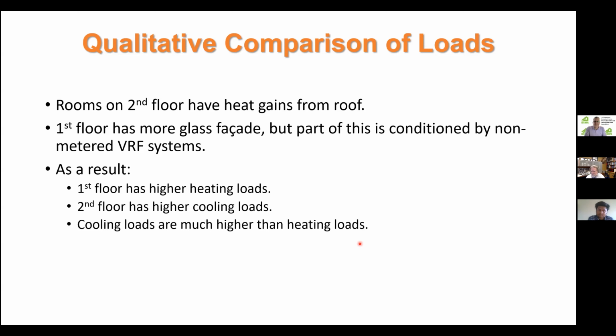So the net effect, which we will come to later: we measured the heating loads. The first floor has somewhat higher heating loads. The second floor has higher cooling loads. But in general, the cooling loads are quite a bit higher than heating loads, as you might expect for an office building in Atlanta, Georgia.